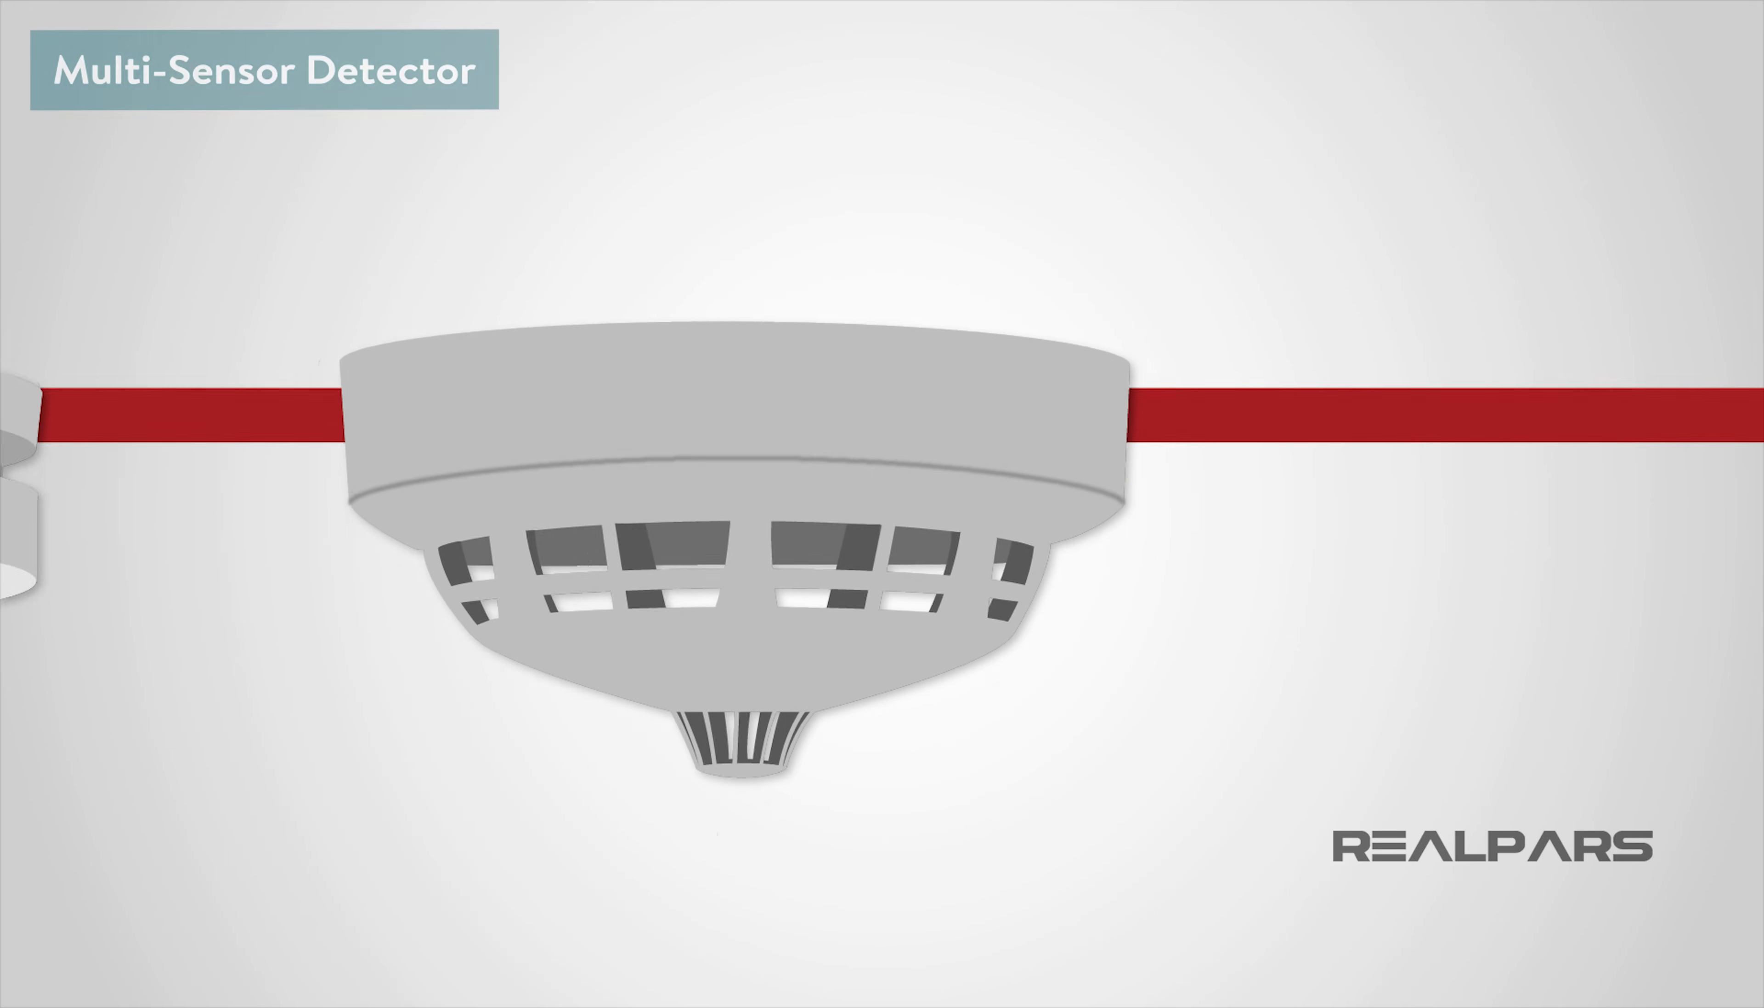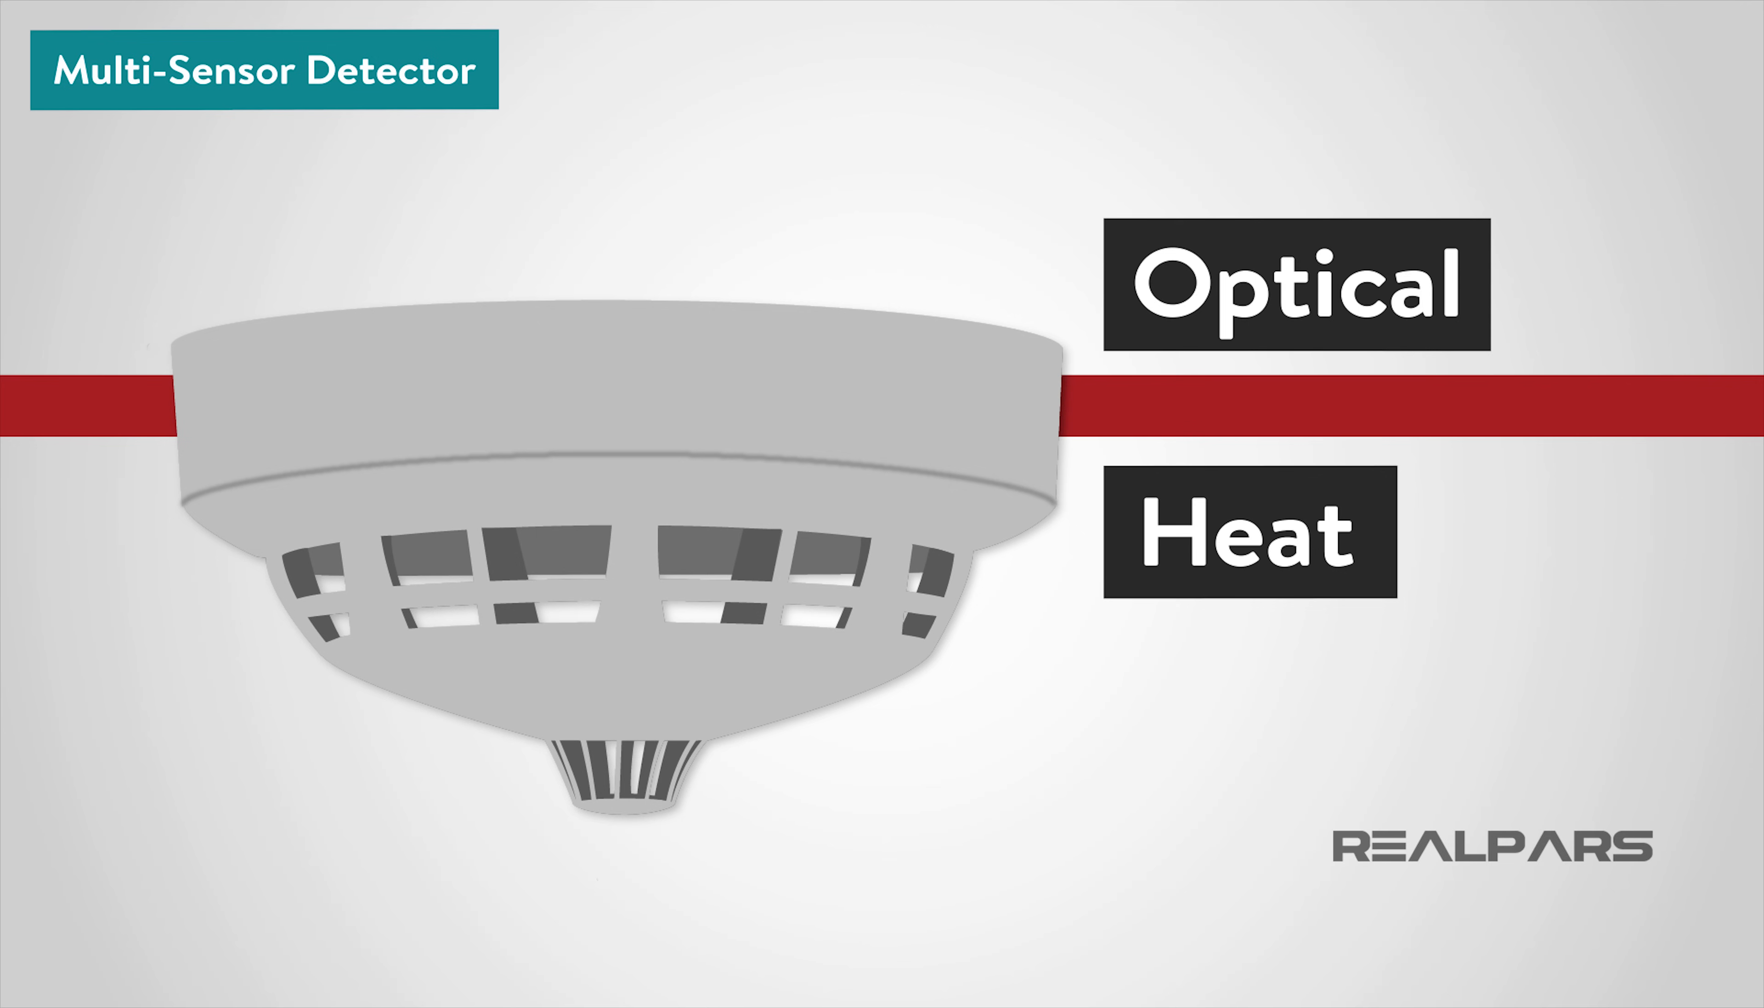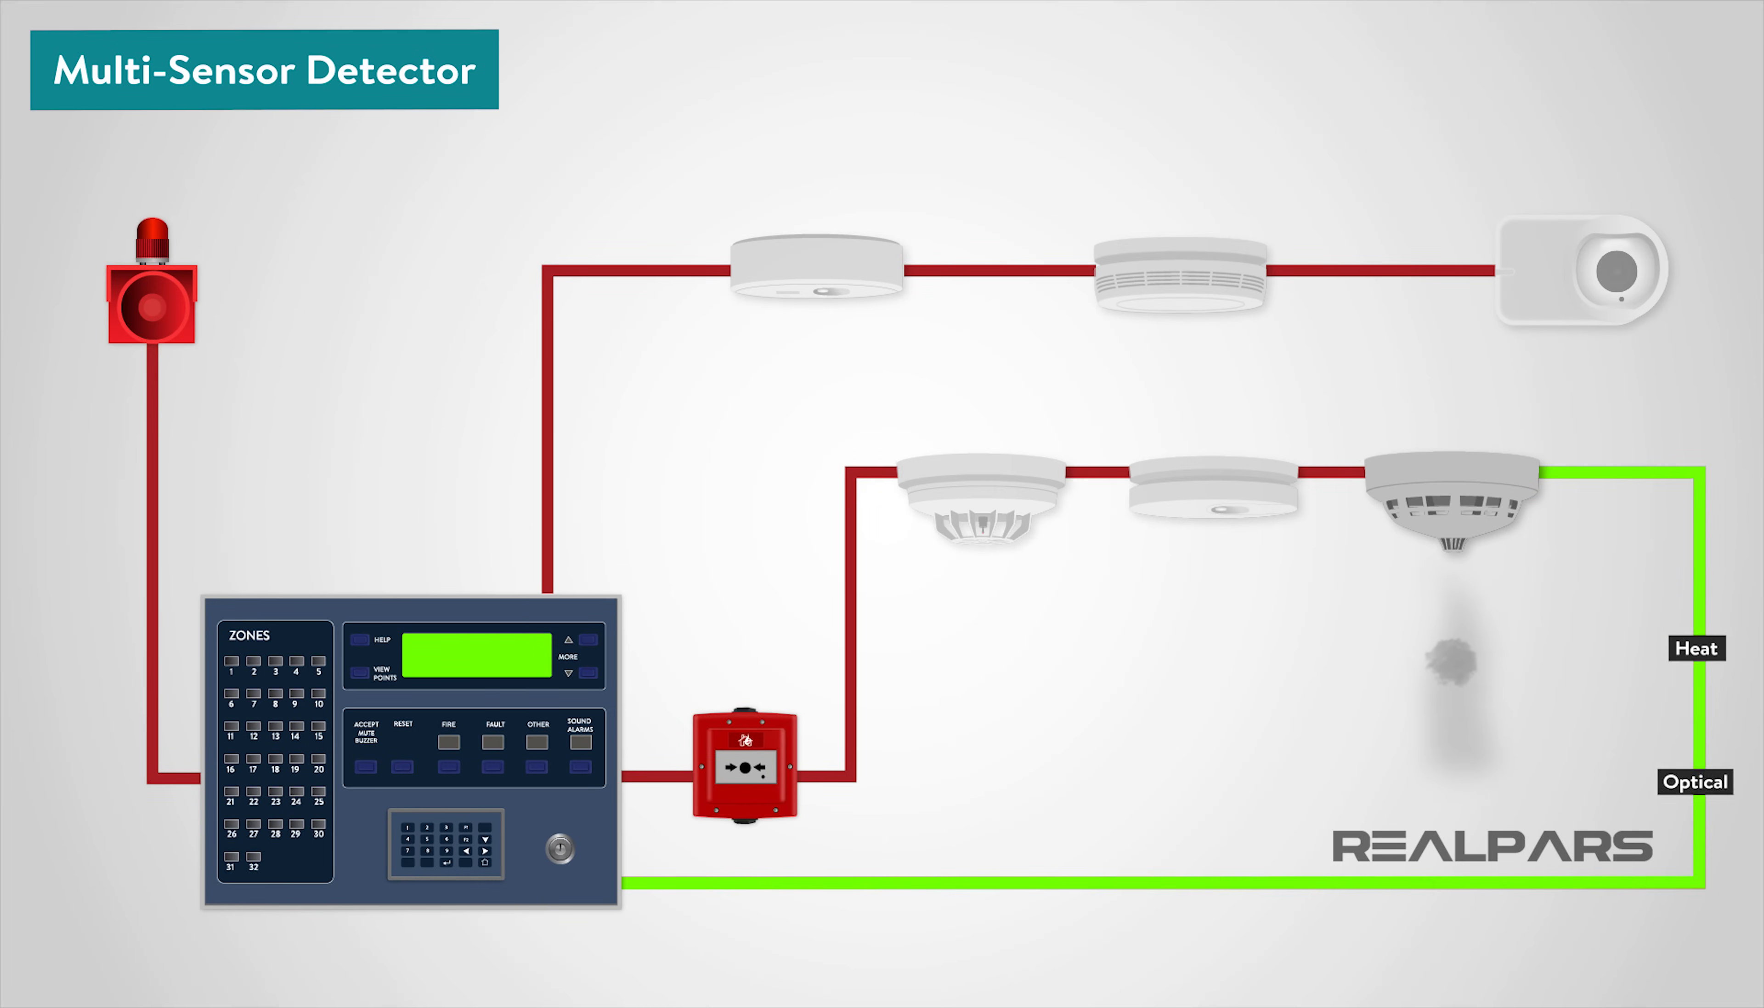The multi-sensor detectors combine inputs from both optical and heat sensors, and process them using a sophisticated algorithm built into the detector circuitry. When polled by the control panel, the detector returns a value based on the combined responses from both the optical and heat sensors. They are designed to be sensitive to a wide range of fires.